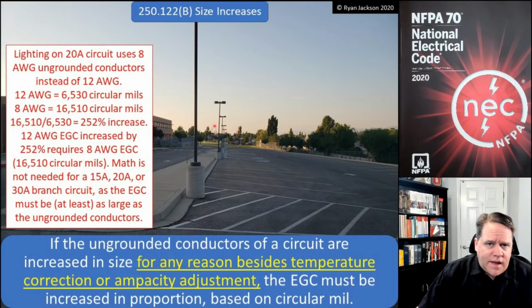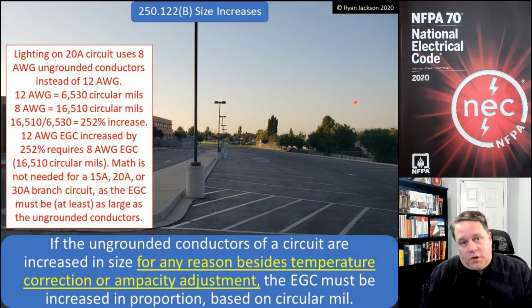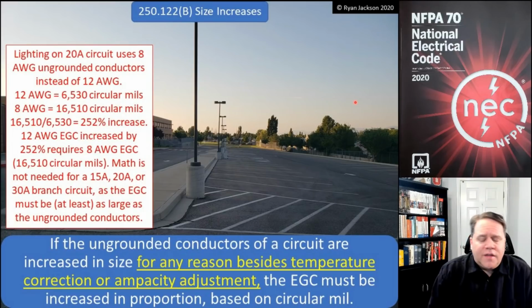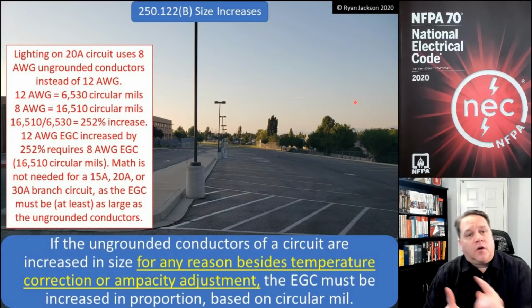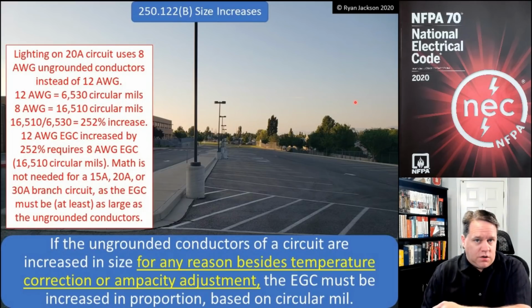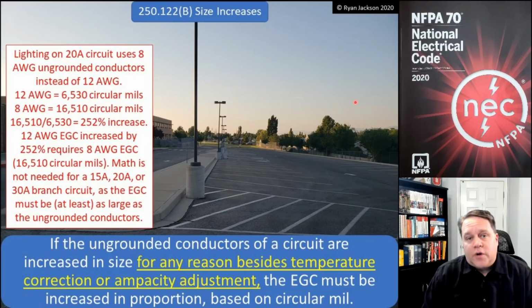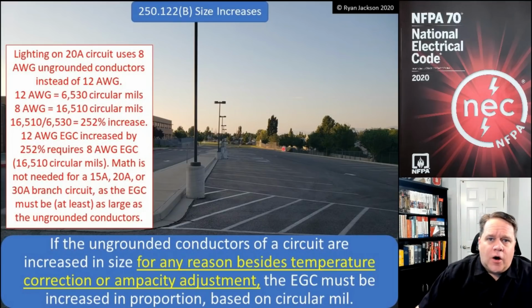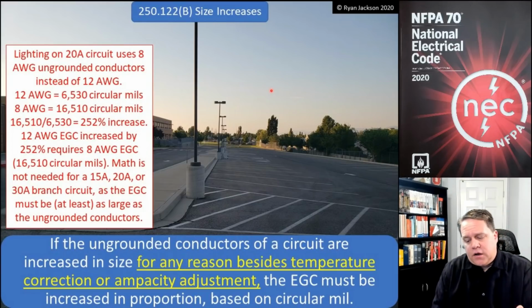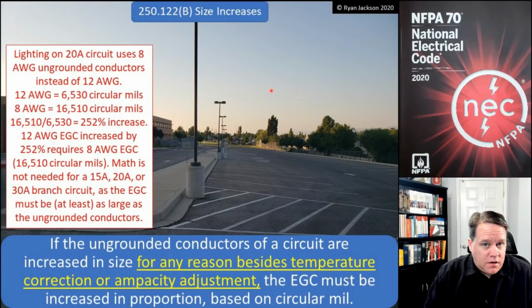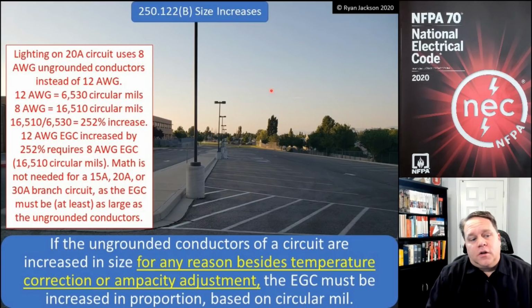So I've got a 20 amp circuit for my lights. But because it's a very long circuit, I use 8 gauge ungrounded conductors instead of the 12 gauge, which would normally be permitted. All right, well, that is an increase in size. That means I need to increase the size of my equipment grounding conductor in proportion to the increase of the ungrounded conductors. Okay, so how am I going to figure out all of this? Well, you go to the code book. In the very back, you go to Table 8 in Chapter 9, and that gives you the circular mil of the different conductors.